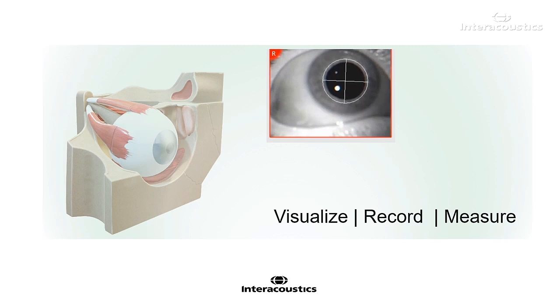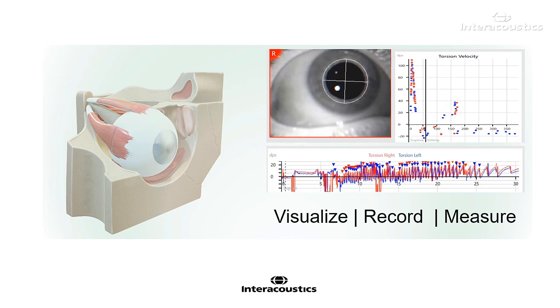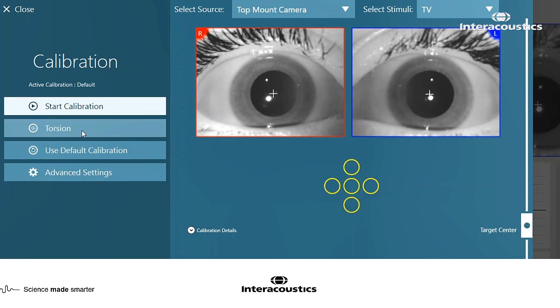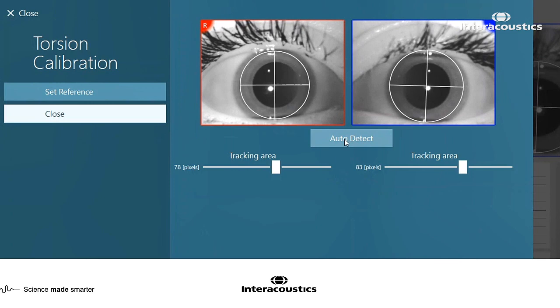Setting the reference on the iris of the eye is paramount to a successful torsional tracking. It's important to set the reference when the goggle cover is already in place and the pupils are dilated, as you will see in the video. Setting the reference is quick and will save time through the evaluation if done correctly at the onset.